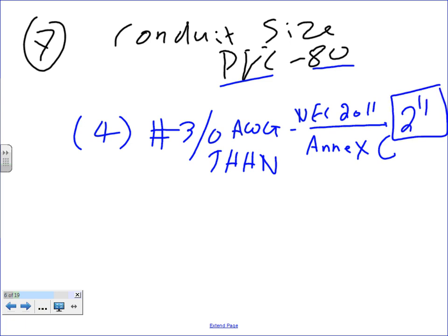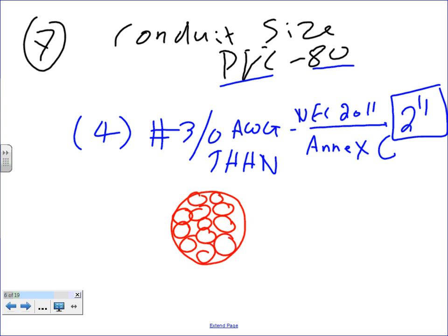Any questions, guys, about this? So no conflict. Yes, sir. What's the difference between maximum number of conductors and maximum number of compact conductors? Compact conductors are a special type of conductor. Most conductors, guys, come as circular stranded conductors. They look like this. Okay, these are the conductors. A compact conductor is specially designed, and they make the stranding different. Can you guys see that? Almost.